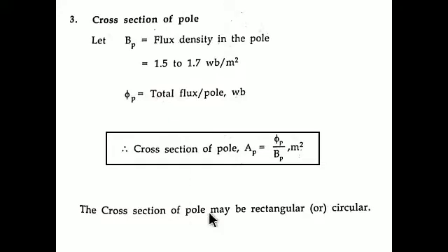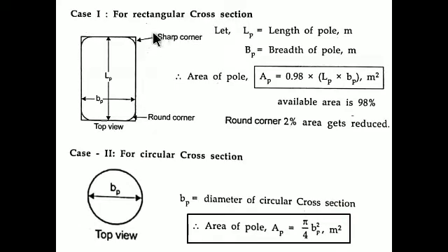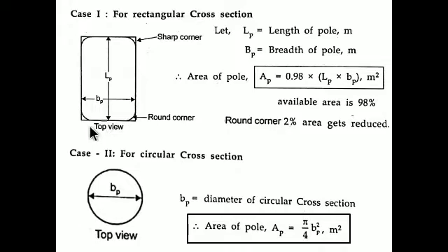There are two types of poles in rotor design: a rectangular pole and a circular pole. For a rectangular cross-section, the formula is Ap = 0.98 × length × breadth of the pole in meter square. The factor 0.98 is used because during designing, the corners are made rounded, which reduces the area by about 2%, so we take 98% of the total rectangular area.